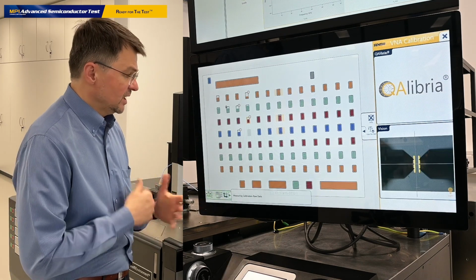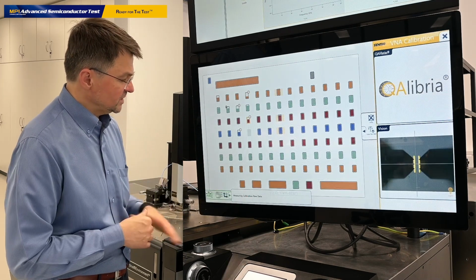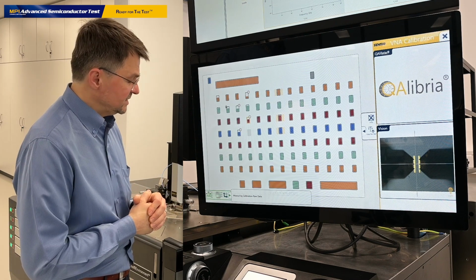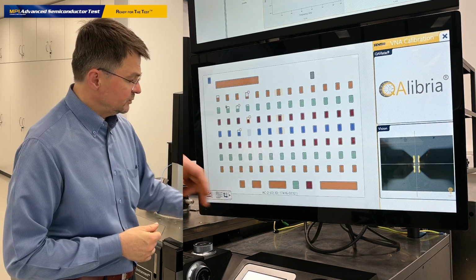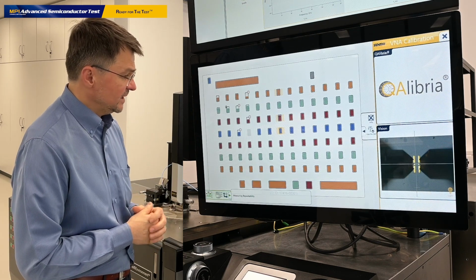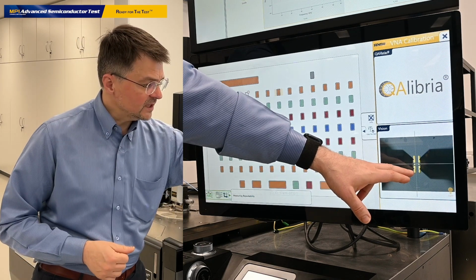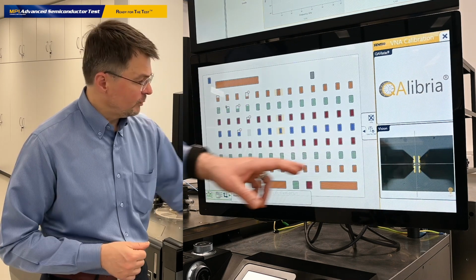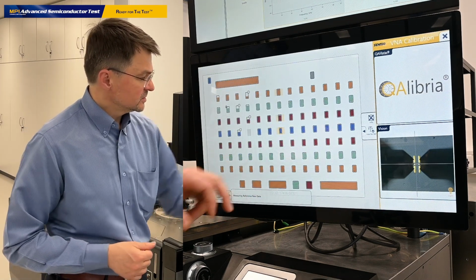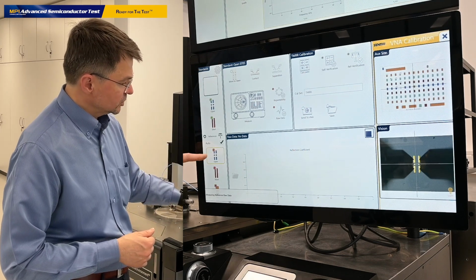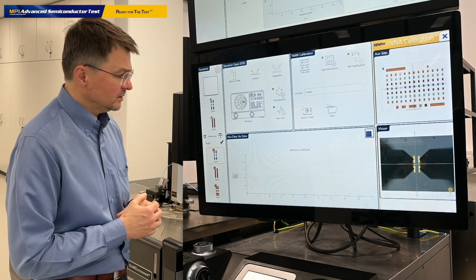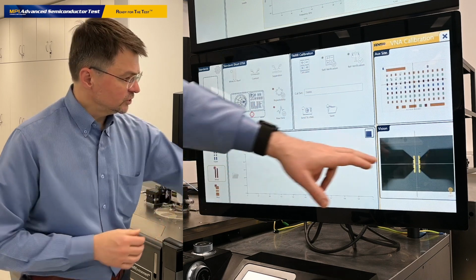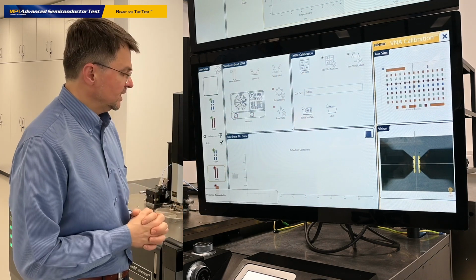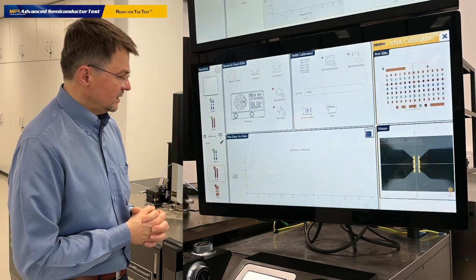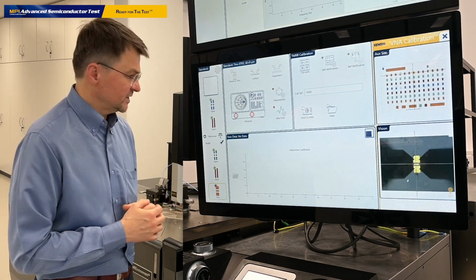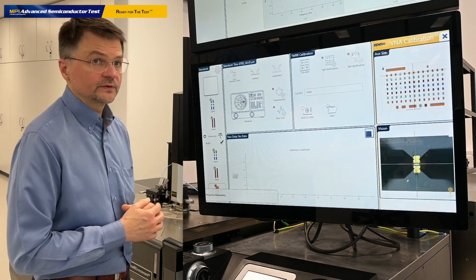We show the messages about what exactly is going on, like measuring calibration raw data, verifying the data repeatability. Then after the data is collected, we compute error terms. We set error terms to the VNA, and now we start measuring our reference elements. You see, we are over the open reference element. This is here. That's what we can also monitor from the execution list of QAlibria. So we go over the open measurement. Then we move to the short, our golden reference short element. And the last element that we selected for such a verification is the through element.